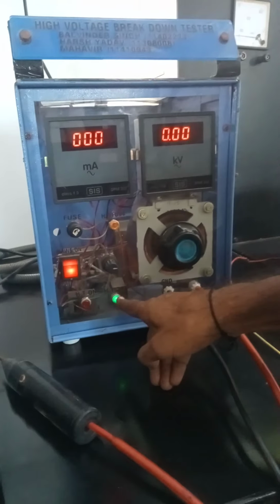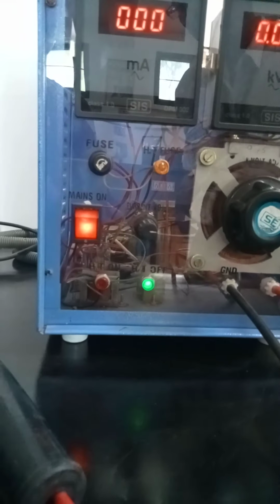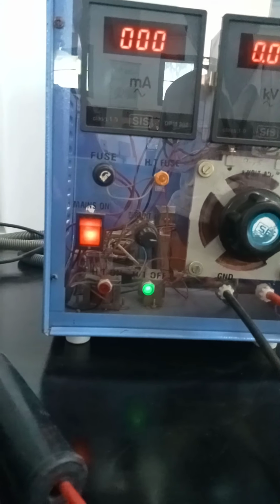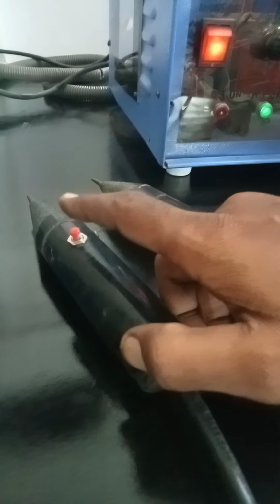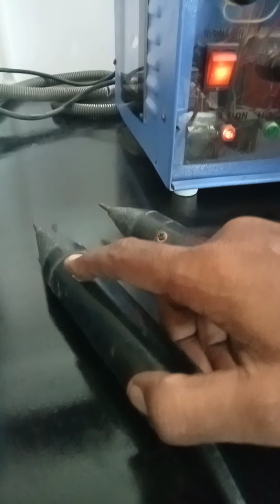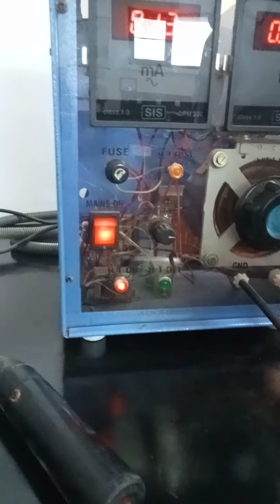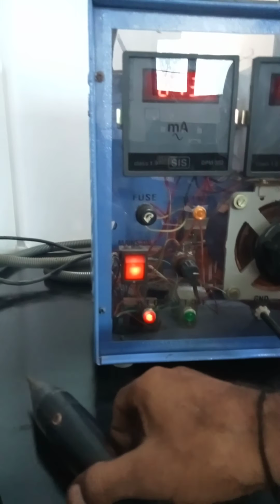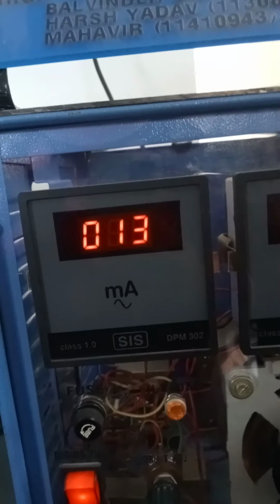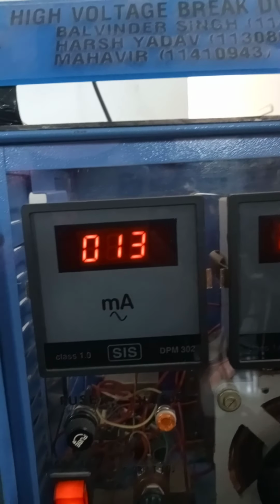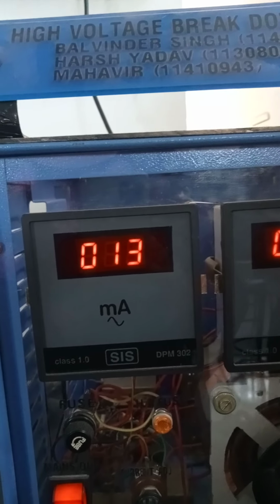So we will switch on the main supply first. We will switch on the mains. Now as you can see, the moment you switch on the mains, you see HT is on, HT is off, and you can see the buzzer. So this is the controlling switch. The moment we press this switch, now our high tension supply is on. No buzzer sound. Now look at the value of ammeter. We have set the value to 13 milliampere.